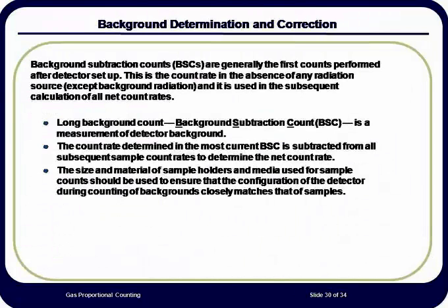A background count time that is much longer than normally expected sample count times can be used to assess both activity and uncertainty. Using a longer background count time will generally decrease the uncertainty contribution to the final activity concentration. However, it should be used with caution since backgrounds can vary slightly over short counting intervals.